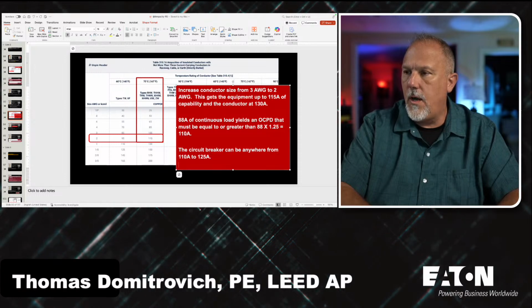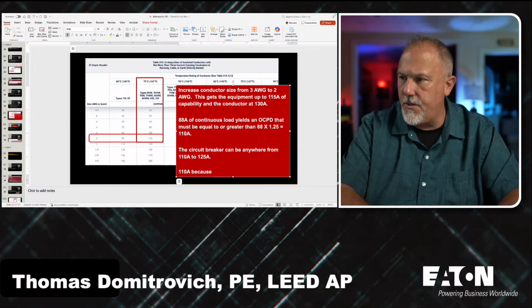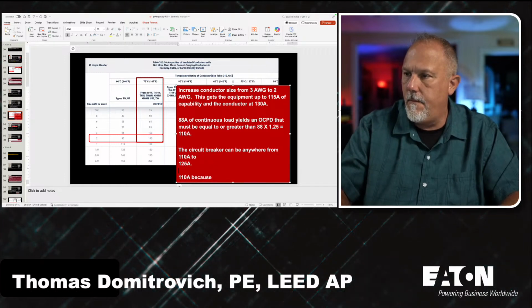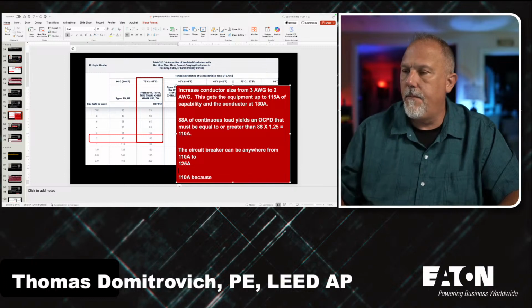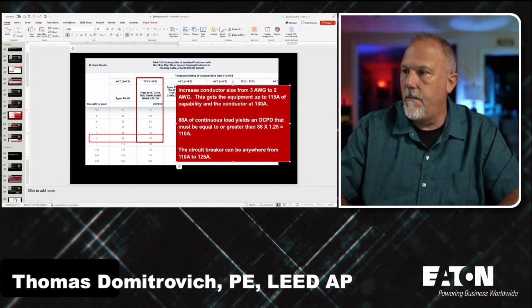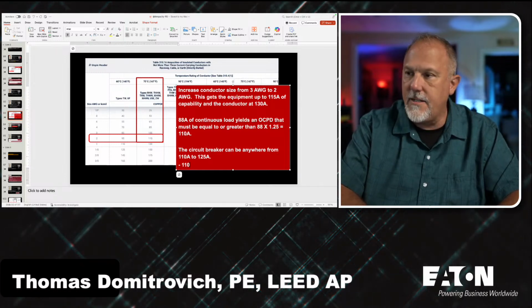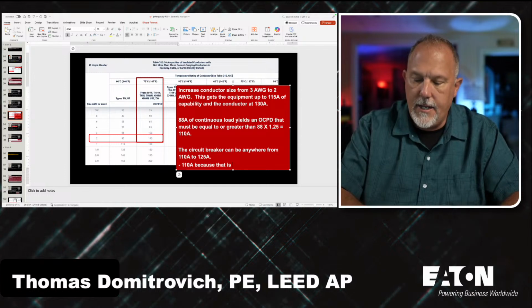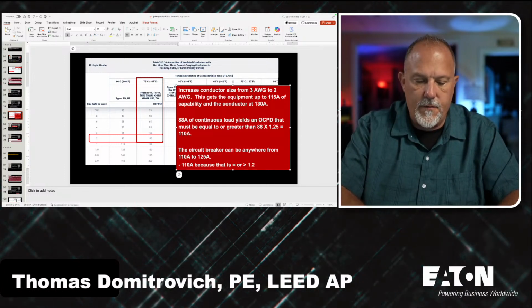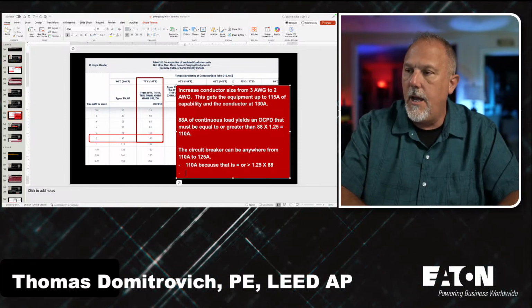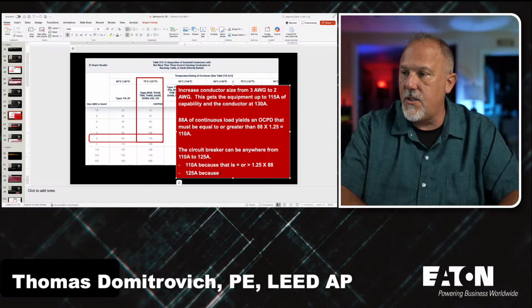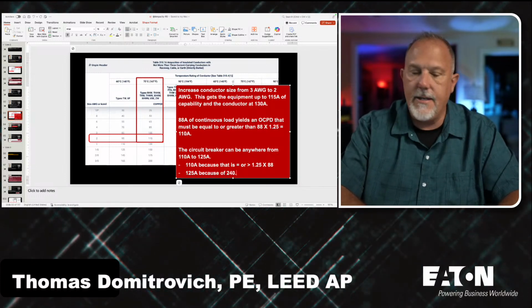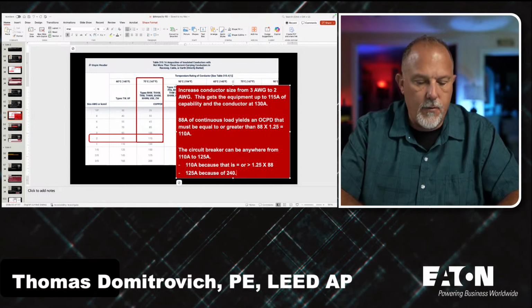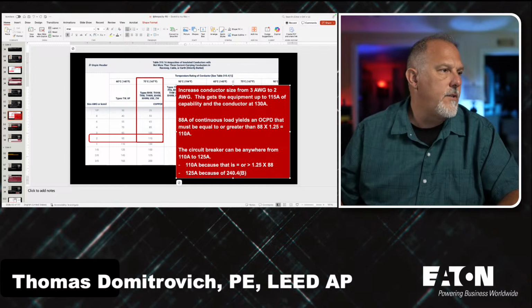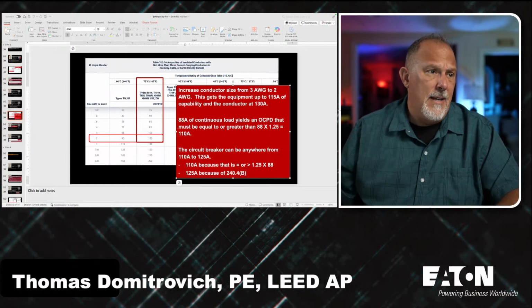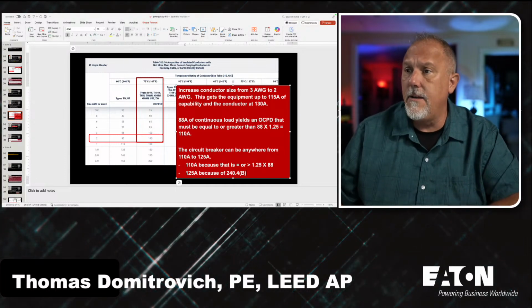Okay, I'll put a note. 110 amps because that is equal to or greater than 1.25 times 88. 125 amp because of 240.4. 240.4b. Is that 240.4b? Yep, 240.4b because I can go to the next higher. So that gives me my range.